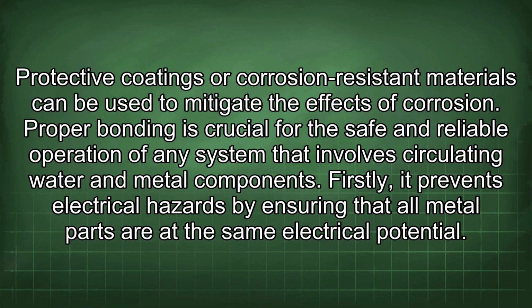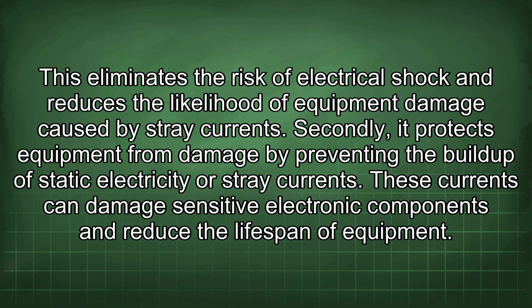Firstly, it prevents electrical hazards by ensuring that all metal parts are at the same electrical potential. This eliminates the risk of electrical shock and reduces the likelihood of equipment damage caused by stray currents. Secondly, it protects equipment from damage by preventing the buildup of static electricity or stray currents. These currents can damage sensitive electronic components and reduce the lifespan of equipment.